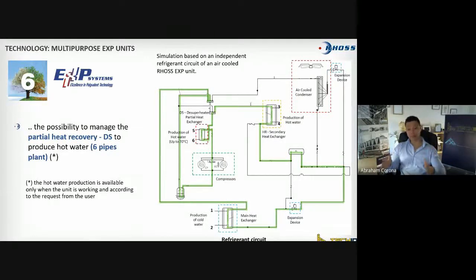So now, what is a 6-pipe system? It's a polyvalent 4-pipe heat pump able to produce extra hot water at higher temperatures, all right? This is an advantage. This is something plus. This is something that I like and I dislike at the same time. The reason is we can control in precision mode the temperature on the main heat exchanger and the temperature on the secondary heat recovery heat exchanger. The problem with this desuperheater is, if you see there, the hot water production is available only when the unit is working and according to the request from the user. That means that temperature is really stuck to the behavior of the load system, or what happens with the compressor load.